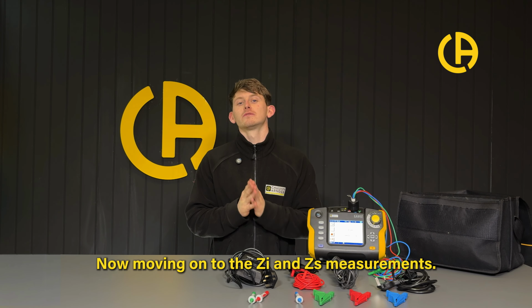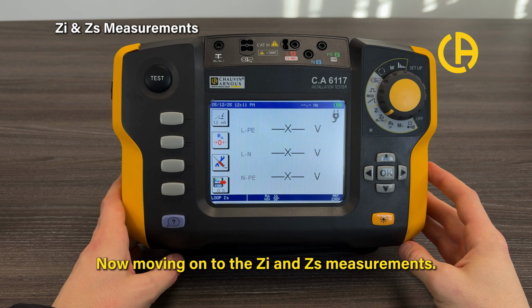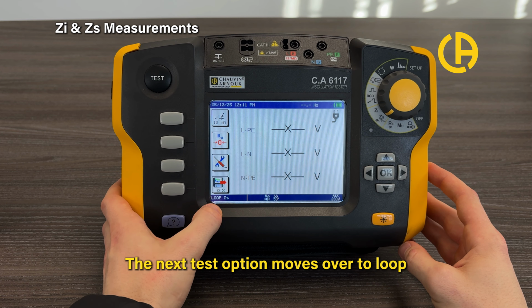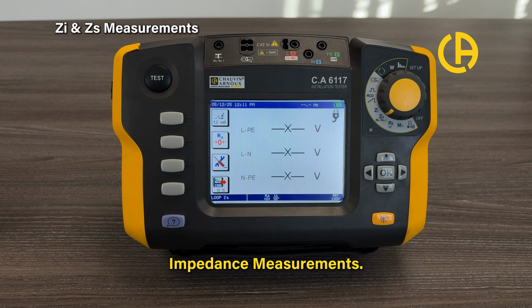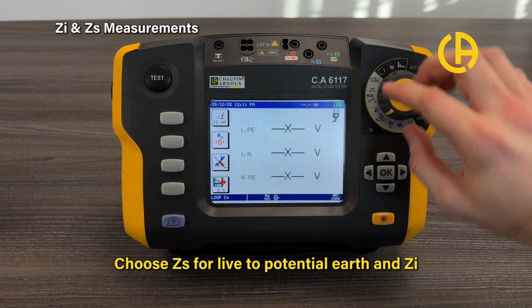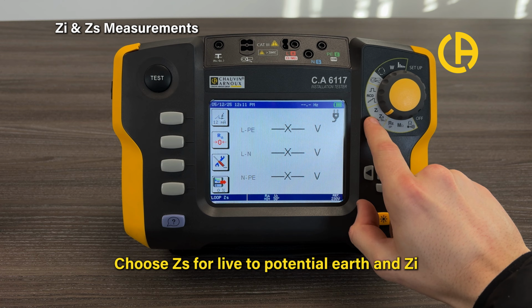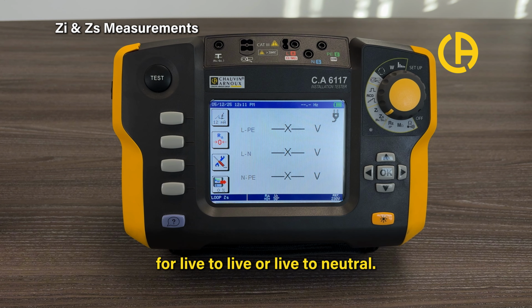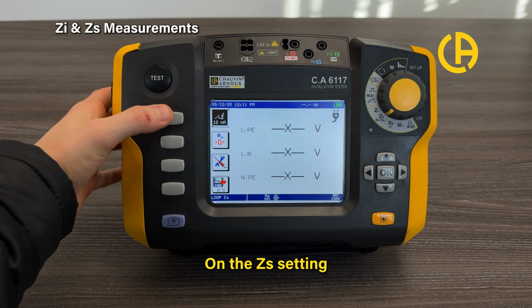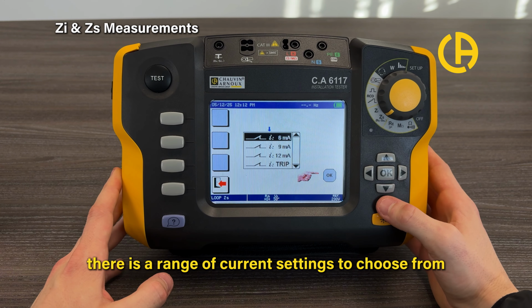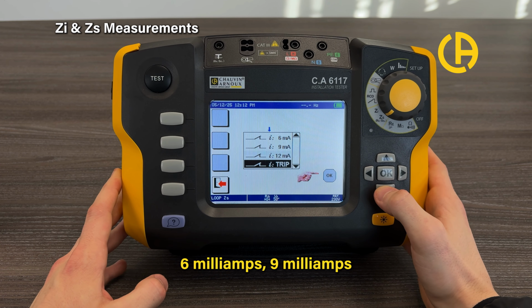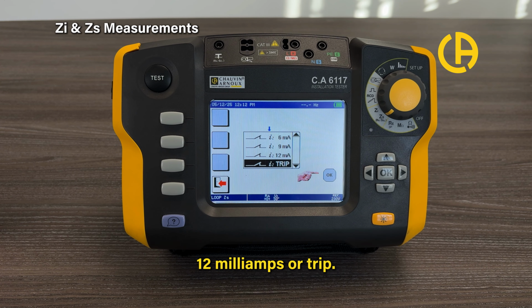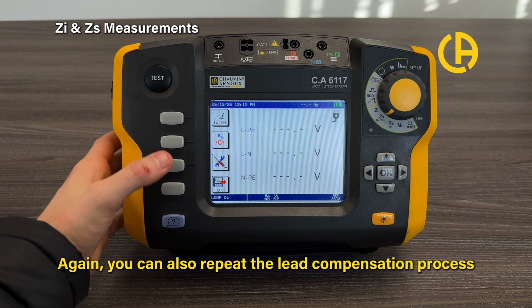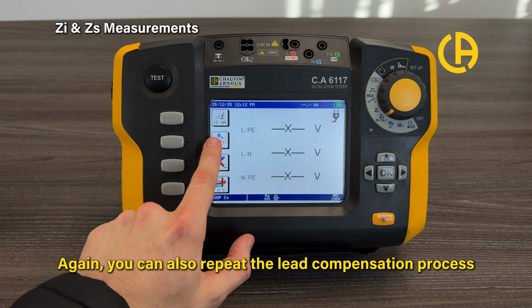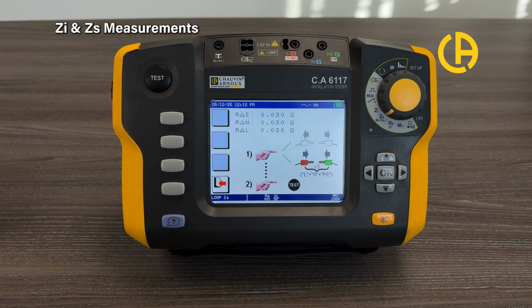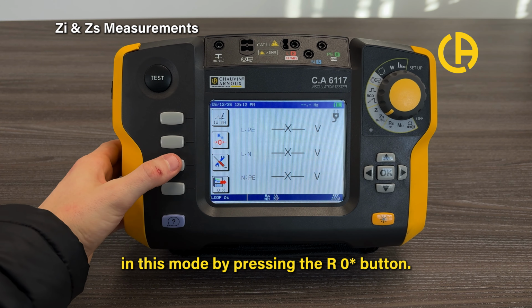Now, moving on to the Zi and Zs measurements. The next test option moves over to loop impedance measurements. Choose ZS for live to potential earth and Zi for live to live or live to neutral. On the ZS setting, there is a range of current settings to choose from: 6 milliamps, 9 milliamps, 12 milliamps, or trip. Again, you can also repeat the lead compensation process in this mode by pressing the R button.